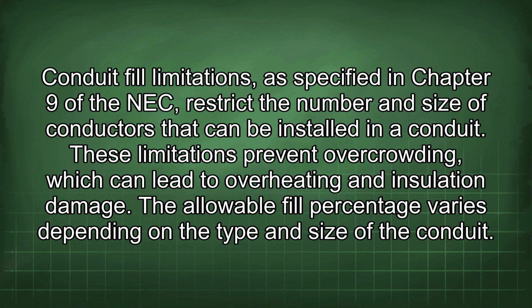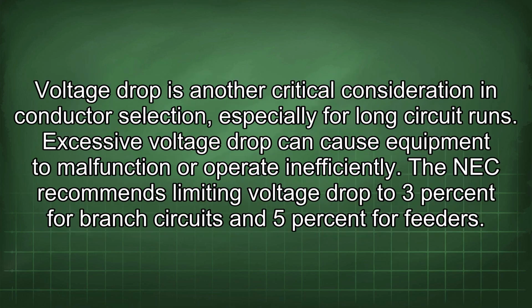Conduit fill limitations, as specified in Chapter 9 of the NEC, restrict the number and size of conductors that can be installed in a conduit. These limitations prevent overcrowding, which can lead to overheating and insulation damage. The allowable fill percentage varies depending on the type and size of the conduit. Voltage drop is another critical consideration in conductor selection, especially for long circuit runs. Excessive voltage drop can cause equipment to malfunction or operate inefficiently.